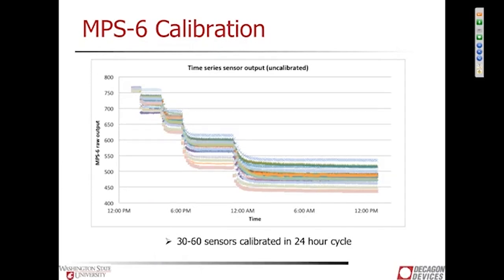And so this is what it ends up looking like if you plot the output of the sensors as we're calibrating them. What you'll see here is that we can calibrate between 30 and 60 sensors in about 24 hours. So this is a huge step forward from the pressure plates that might take a week or 2 weeks to reach equilibrium at these different steps. 24 hours seems like a long time, but in terms of water potential equilibration, it actually is a relatively short period of time. You also see here that these are the uncalibrated output from the sensors, and there's quite a bit of scatter in that output.